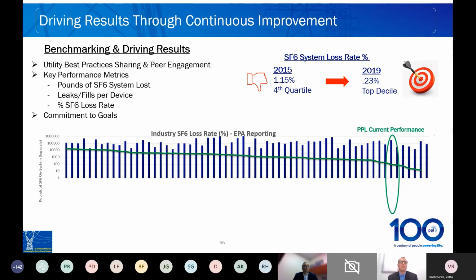Some of the key performance indicators we look at when measuring performance are industry standards. Examples include overall pounds of SF6 lost, leaks and fills per device, and the most targeted, which is an overall percent of your SF6 loss rate. The reason we feel this is a good metric is it provides an overall comparison of your actual SF6 loss versus your actual system capacity, very similar to a health index in a sense.